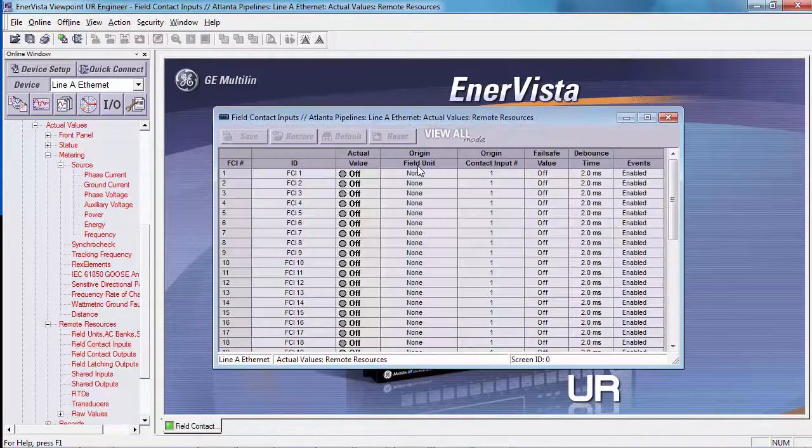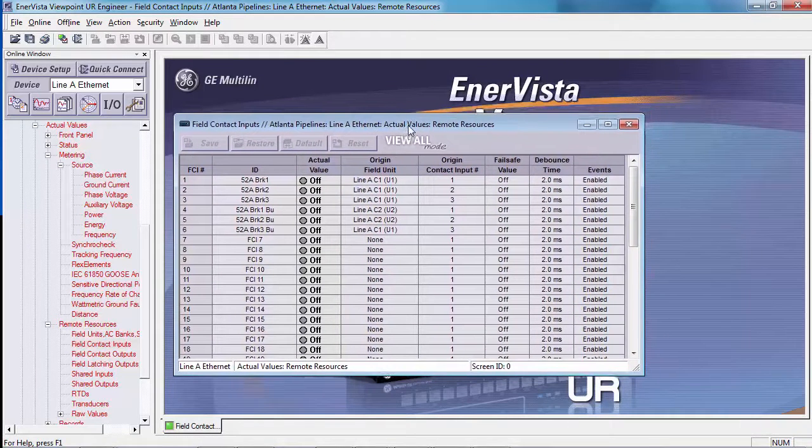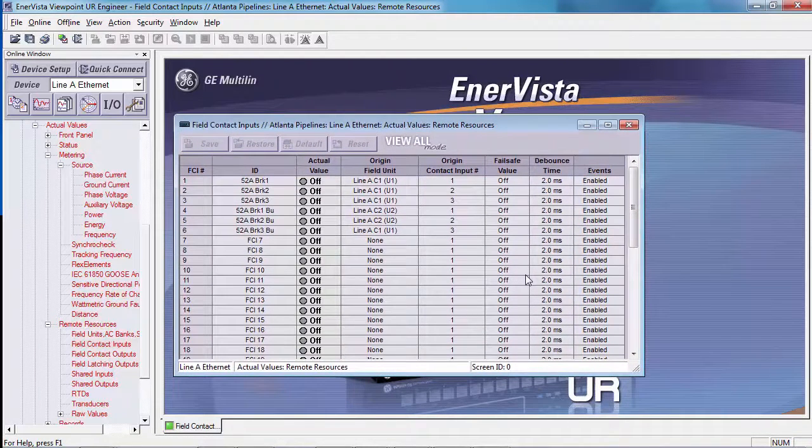Take a look at the contact inputs. If I close switch 1 on the box, then we can see that the status has changed. If I close switch 2 and close switch 3. Now, why is it showing up in two places? The reason it's showing up in two places is because we're monitoring the same brick contact input changes from two different cores. This one is from core 1. This one is coming in from core 2.